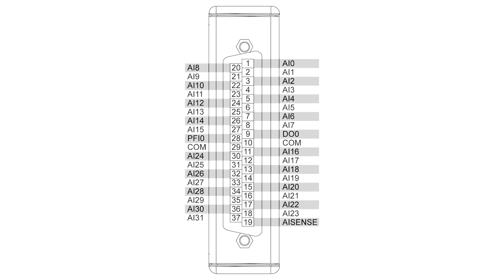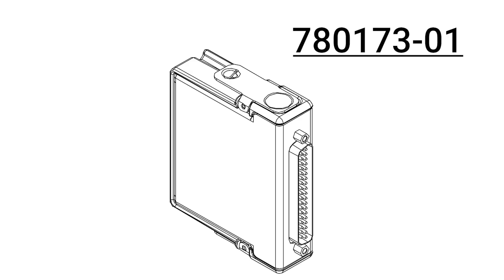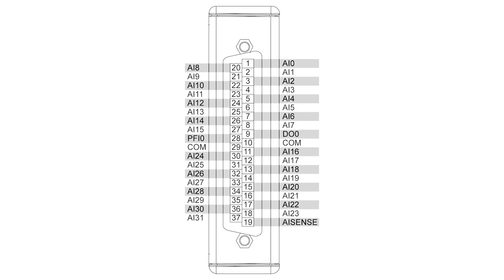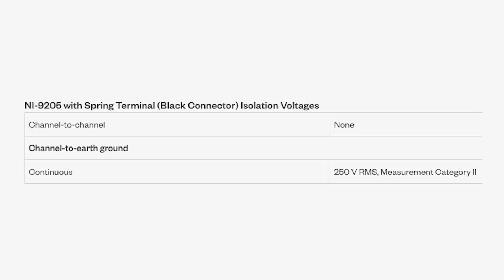Finally, part number 780173-01 has D-sub front connectors, but is the only version that is conformally coated. The variations with D-sub connectors have 60V DC channel-to-earth ground isolation, while the module with spring terminal connectors has 250V RMS channel-to-earth ground isolation.